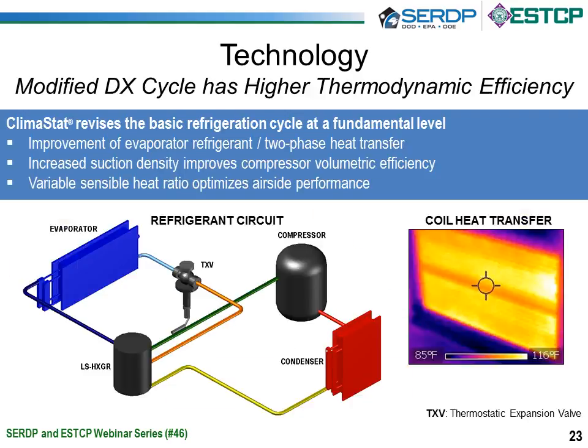So ClimaStat modifies the cycle by adding an additional component, which is right here. This is the liquid suction heat exchanger separator device. It has no moving parts. It's simply a heat exchanger container. And essentially what it does is subcool the refrigerant, or make it colder, before it reaches the TXV. So instead of it being 100 degrees liquid refrigerant, it would be, say, 75 degrees.